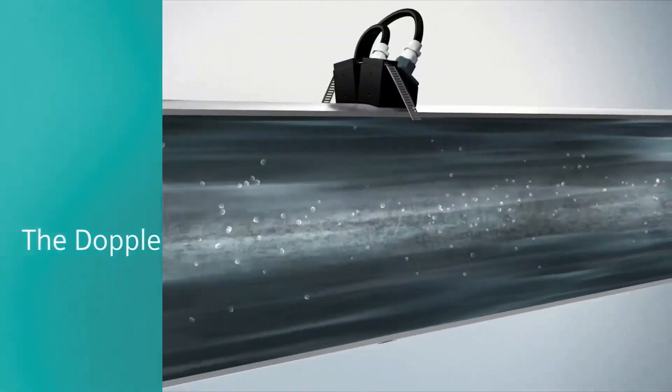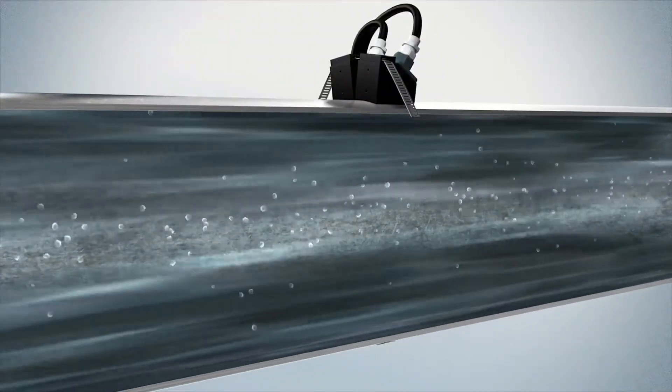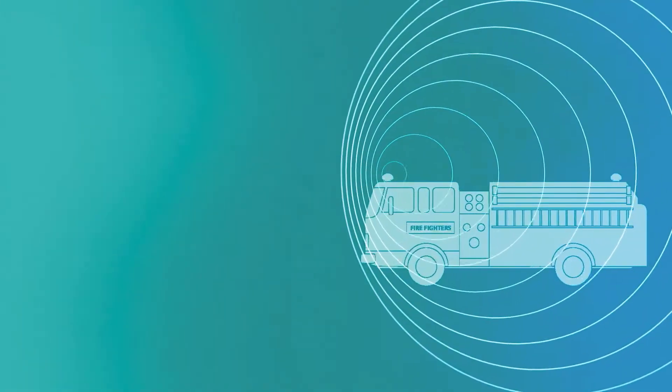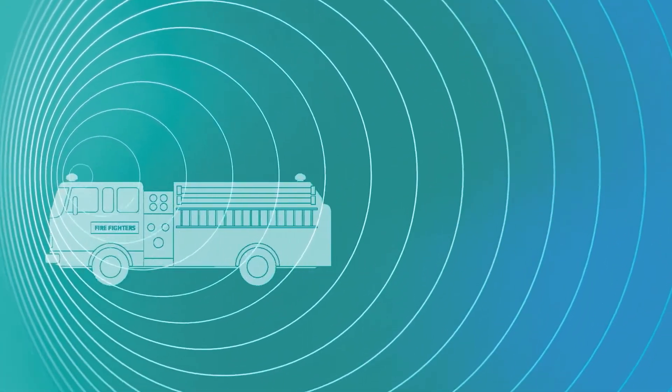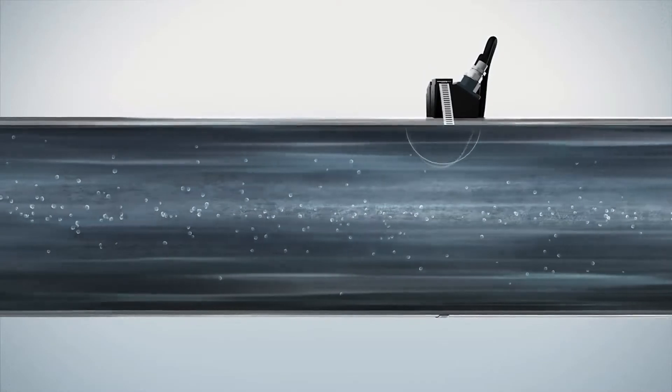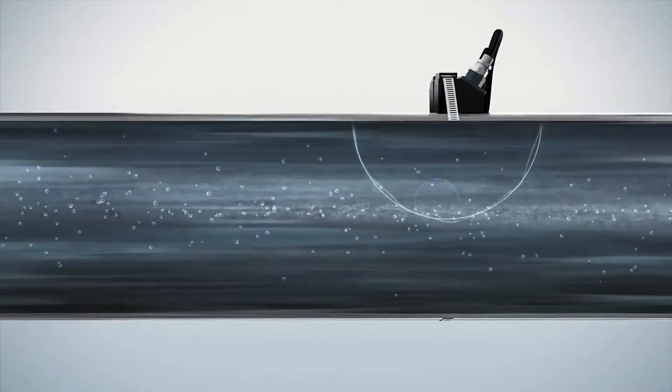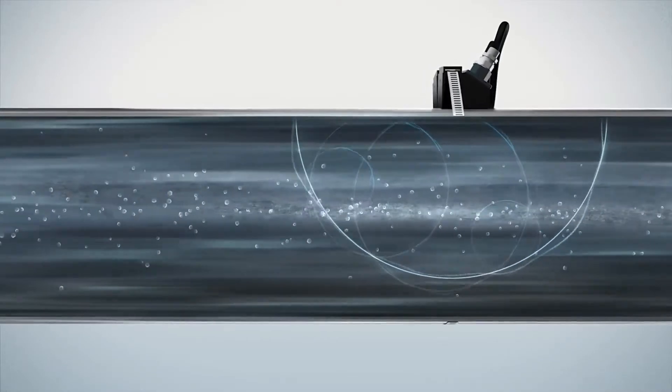Siemens uses a method based on the Doppler effect, a frequency shift similar to a passing fire engine. When an ultrasound wave hits the particles, the sound waves are reflected and the wavelength shifts based on the particle speed.